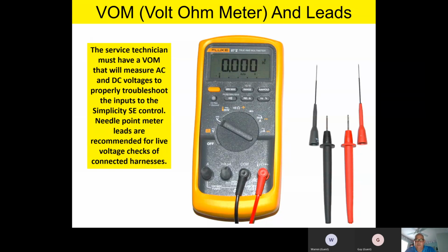But if the technician is going to be working on the Simplicity control, he's going to need to be able to take DC voltages and AC voltages to properly diagnose, especially sensors. In addition, I'm going to recommend that you buy a set of needlepoint meter leads. Again, what you're looking at here are tools out of my own personal tool bag. Those needlepoint meter leads on the right-hand side are extremely sharp. They work really well for taking live voltages down into a harness. If you've got a harness plugged into a sensor, or plugged in like on your thermostat inputs, you can dig those little needlepoint leads down inside that harness and read what the voltage is with the sensor plugged in.